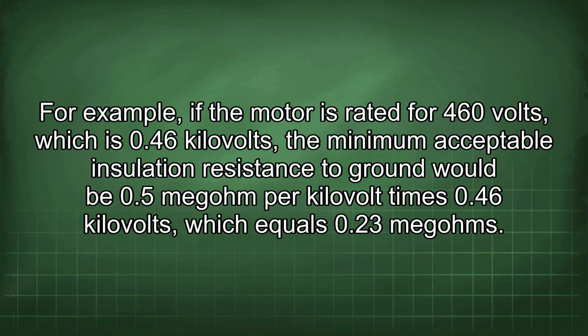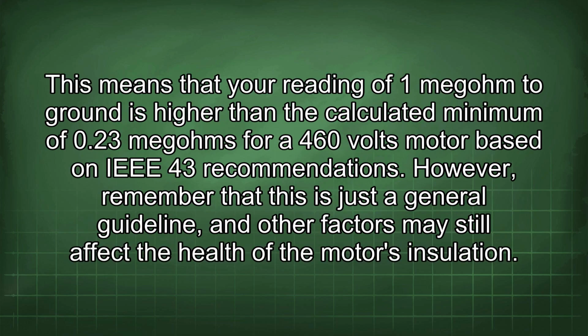For example, if the motor is rated for 460 volts, which is 0.46 kilovolts, the minimum acceptable insulation resistance to ground would be 0.5 megohm per kilovolt times 0.46 kilovolts, which equals 0.23 megohms. This means that your reading of 1 megohm to ground is higher than the calculated minimum of 0.23 megohms for a 460 volts motor based on IEEE 43 recommendations.